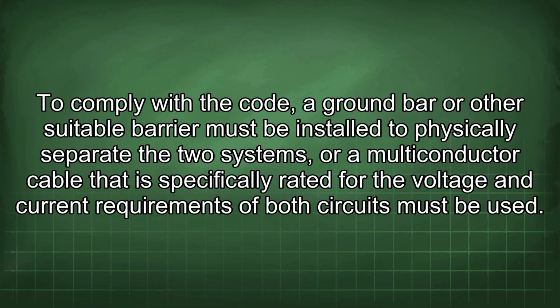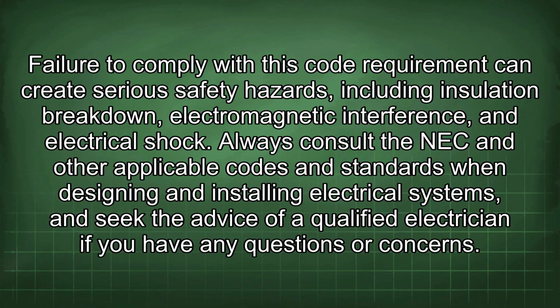To comply with the code, a ground bar or other suitable barrier must be installed to physically separate the two systems, or a multi-conductor cable that is specifically rated for the voltage and current requirements of both circuits must be used. Failure to comply with this code requirement can create serious safety hazards, including insulation breakdown, electromagnetic interference, and electrical shock. Always consult the NEC and other applicable codes and standards when designing and installing electrical systems, and seek the advice of a qualified electrician if you have any questions or concerns.